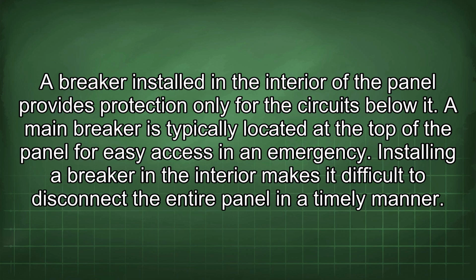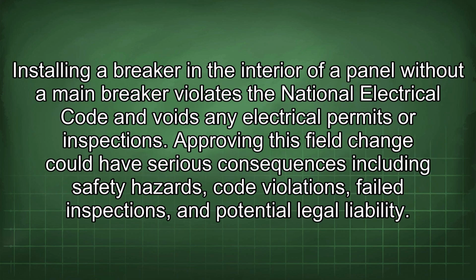A main breaker is typically located at the top of the panel for easy access in an emergency. Installing a breaker in the interior makes it difficult to disconnect the entire panel in a timely manner. Installing a breaker in the interior of a panel without a main breaker violates the National Electrical Code and voids any electrical permits or inspections. Approving this field change could have serious consequences, including safety hazards, code violations, failed inspections, and potential legal liability.